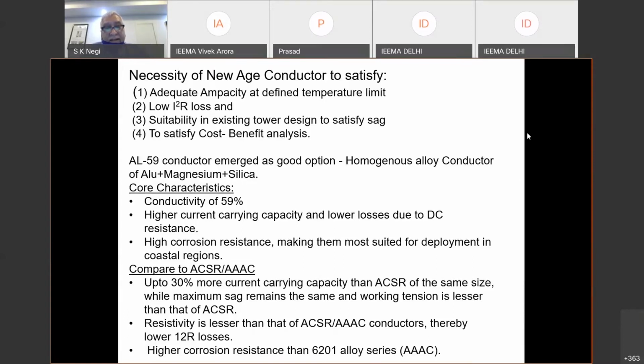Now, having said the characteristics of the AL59, when we compare with the ACSR Moose conductor, it carries 30% more current, and that too at a temperature of 95, while maximum sag remains the same, and working tension is lesser than ACSR. So this is the very, very important factor which triggers the thinking process toward the AL59. Resistivity is lesser than that of ACSR and AAAC conductors, thereby lower I square R losses, and higher corrosion resistance, as I already said. So this is the background under which AL59 has an edge over the ACSR conductor.